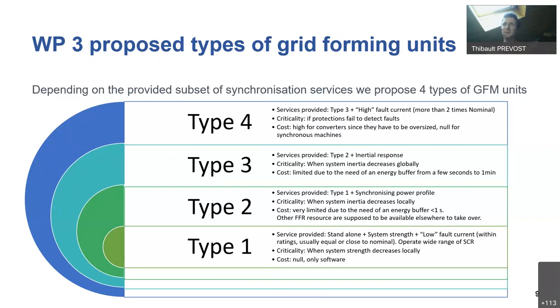Then type three would be the same, but with inertial response. The inertial response is the same, but you would need more energy stored because the inertial response will last for a few seconds. You would need such a kind of type three grid forming when the system inertia globally decreases. And you have this type four grid forming, which is in fact type three with very high fault current. So this is needed when traditional protection fails to detect a fault and you can't upgrade the protection scheme. Basically, it would be a synchronous machine.